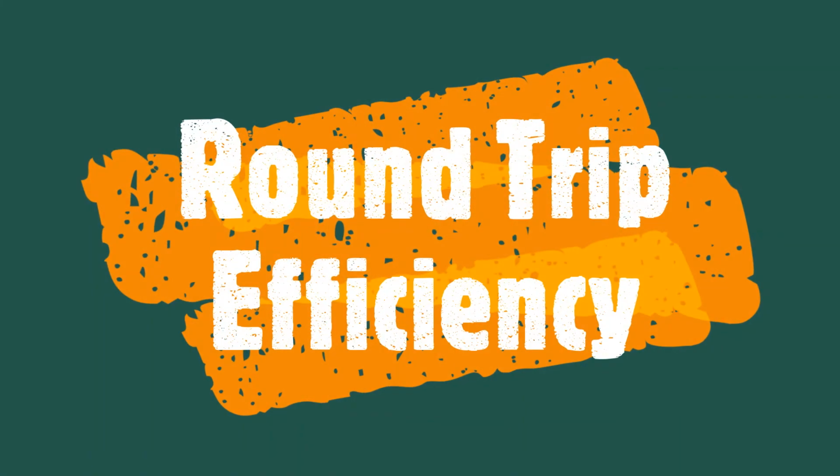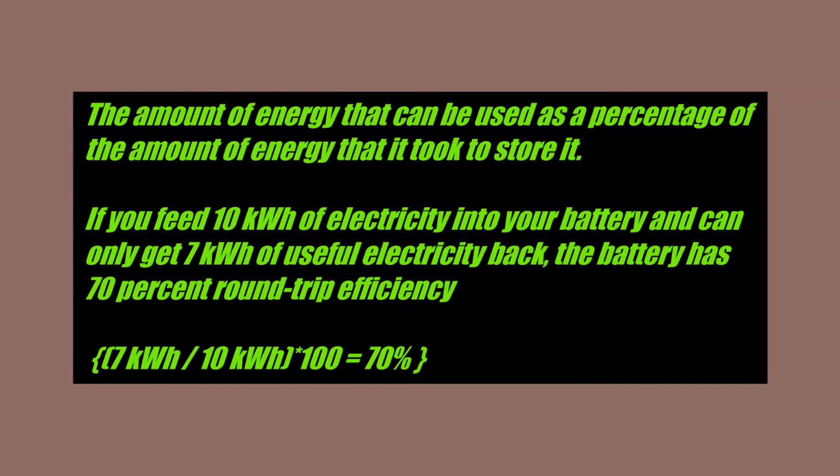Next important parameter is the round trip efficiency. This parameter shows how efficient your battery is over a complete charge and discharge cycle. It represents how much energy you will use to fully charge your battery, and then what portion of that spent electricity can you recover from the battery. For example, if you feed 10 kilowatt hours of electricity to fully charge a battery and can only get 7 kilowatt hours back from the battery, then it has an efficiency of 70%.